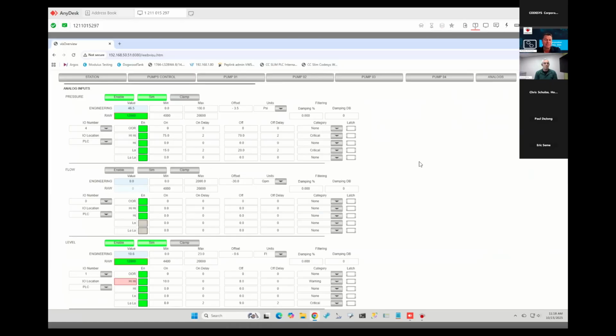So what latching means, for everybody that doesn't know, is once that alarm happens, someone has to acknowledge it before that pump will restart. If we don't latch it, critical means it will shut the pumps down, but once it comes back to an offset point, it will restart the pumps. This is very important also, because in a lot of cases, they might have an issue with their tanks. So in this particular customer that we're looking at here, if the tank gets too low, they can't run the booster pumps. So that means they want to shut the booster pumps down.